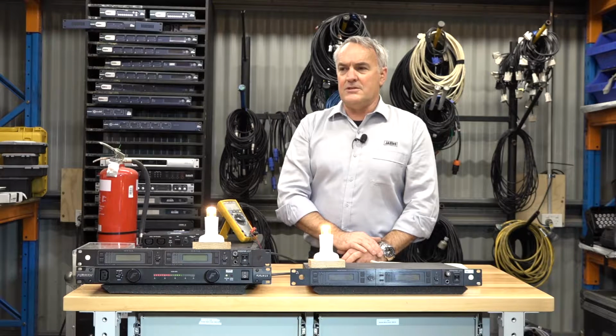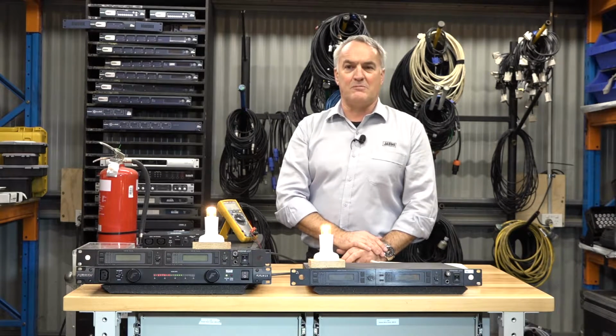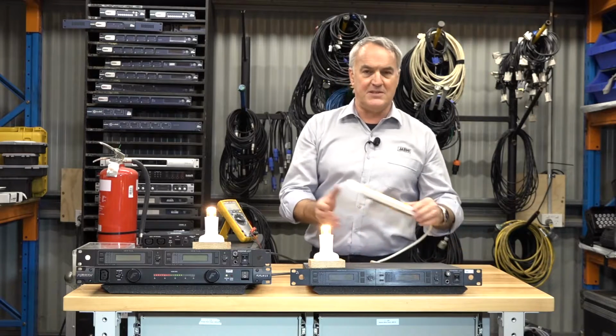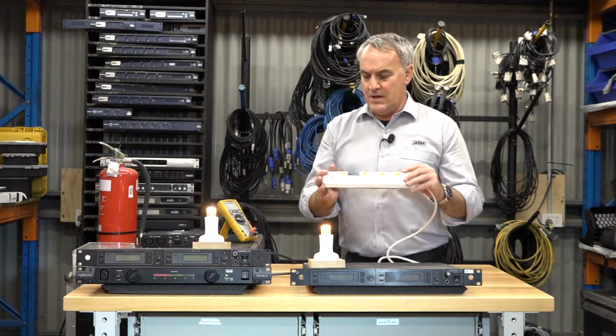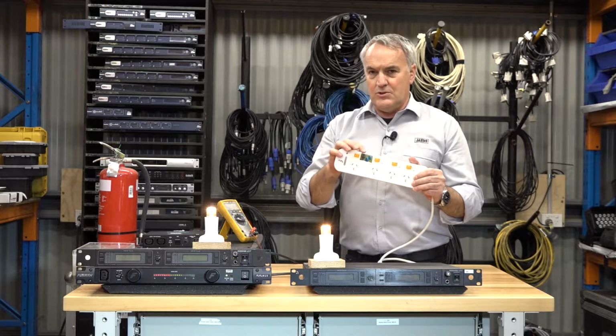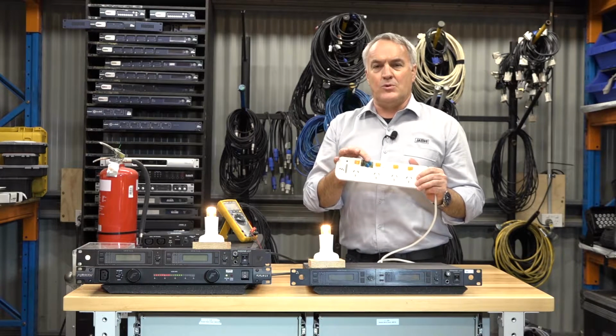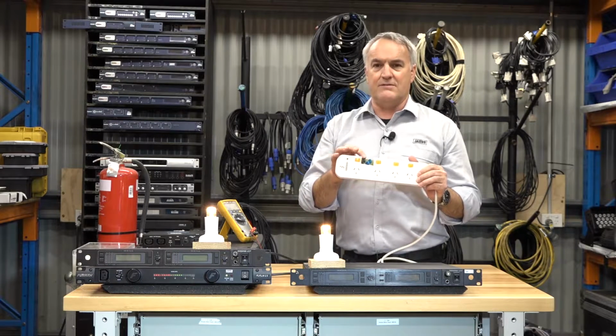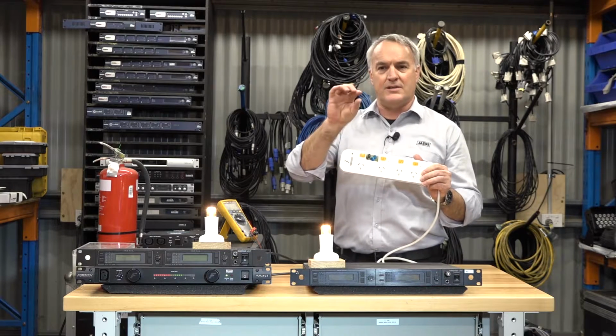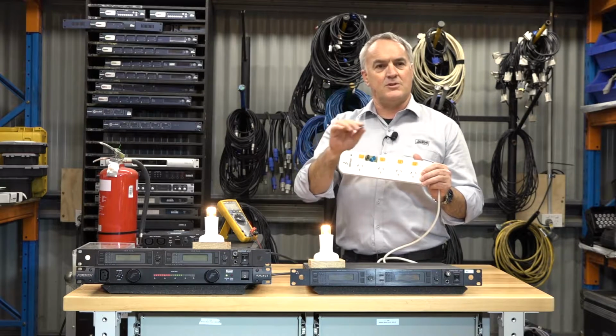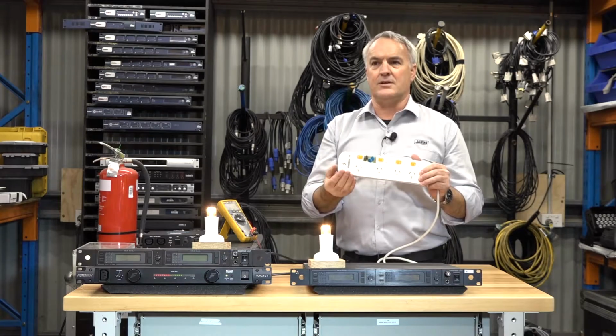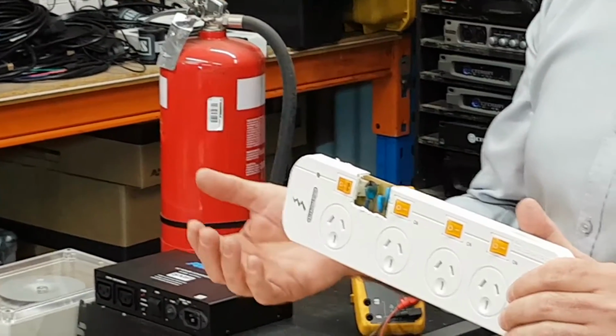You can often see products on the market that claim to give you this level of protection, often in sort of domestic power strips like these. The way they work is they use a semiconductor component called an MOV, a metal oxide varistor, and it's trying to shunt any high voltage spikes around your connected equipment. And they do it moderately well.